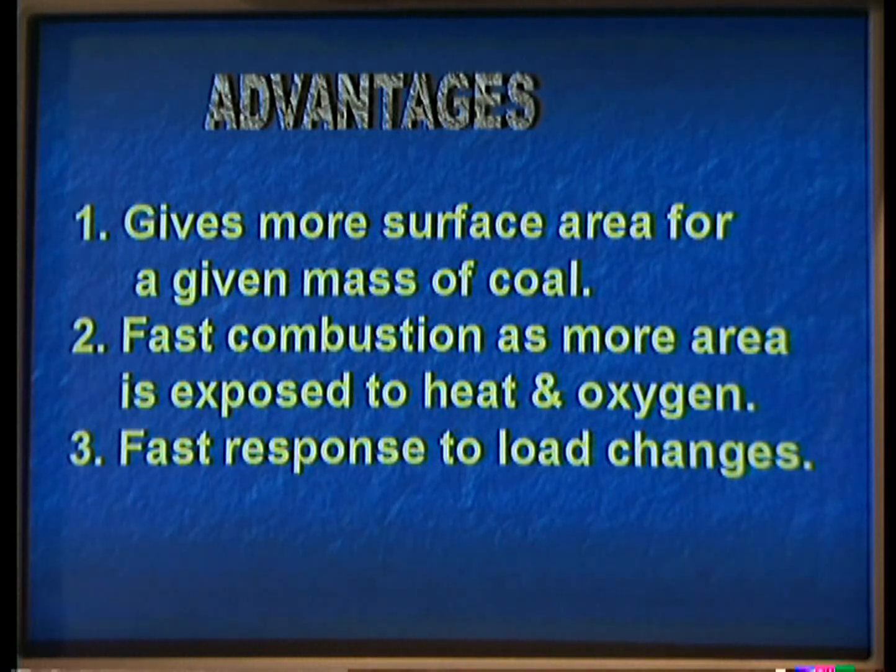This is the process. Next, the third one, fast response to load changes. That means as per our requirement, whether the load demand is more or low, depending upon the load demand, we can easily change the combustion quantity. Suppose load demand is more, we have to spray more coal into the furnace. If load is suddenly decreased, then we have to regulate the quantity of pulverized powder. This is the third advantage of pulverization.